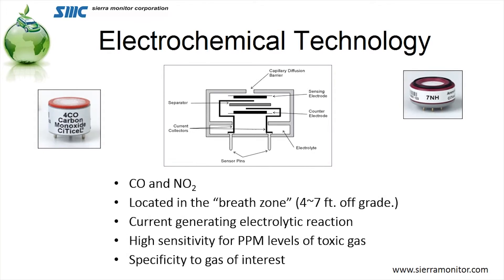Electrochemical devices — those we use for CO and for nitrogen dioxide — are located in the breathe zone, which in my case is four feet and in some other people's cases as high as seven feet, but generally in that area where you're going to be breathing. They generate electric current based on the amount of chemical that's around them. They're highly sensitive for parts per million of toxic gases, and they're specific to the gas of interest: CO or NO2.